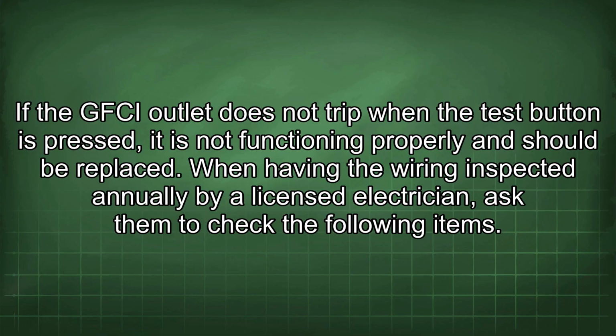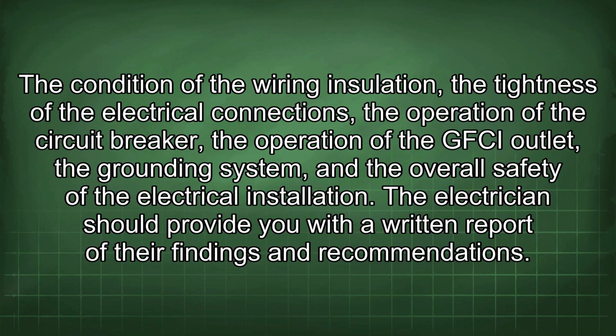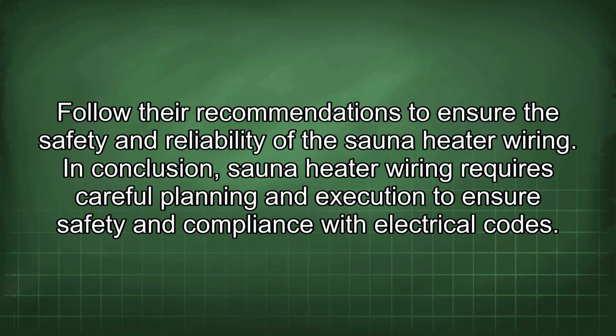When having the wiring inspected annually by a licensed electrician, ask them to check the following items: the condition of the wiring insulation, the tightness of the electrical connections, the operation of the circuit breaker, the operation of the GFCI outlet, the grounding system, and the overall safety of the electrical installation. The electrician should provide you with a written report of their findings and recommendations. Follow their recommendations to ensure the safety and reliability of the sauna heater wiring.